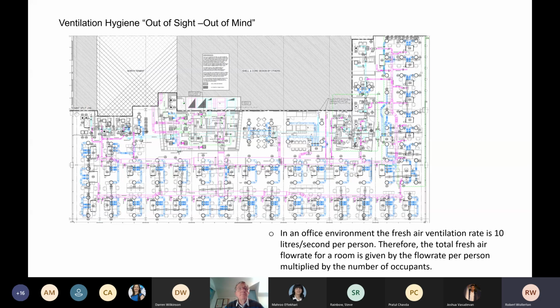Here you can see a typical layout, and office users and building users may not fully appreciate what is above the ceiling tiles, the pop-up ceiling tiles. This shows a ductwork layout and the expanse of it within an office area. Here you've got primary ductwork marked as pink, I think it is, and that's serving fan coil units. You've got open ends here which serve another filtered unit, fan coil units, in the office environment. And the recommendation in an office environment is a fresh air ventilation rate of 10 litres a second per person. That is the advice given here.